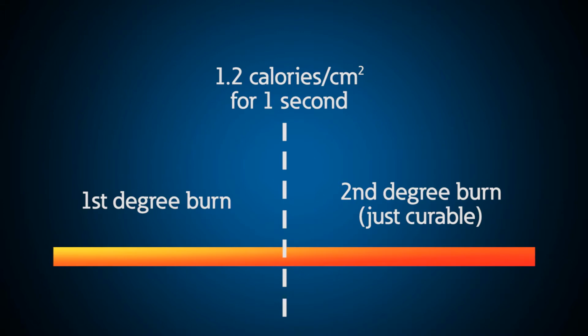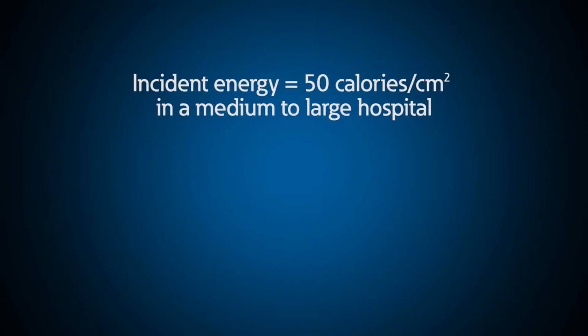It takes 1.2 calories per centimeter squared for 1 second impinged upon human skin to reach the threshold between a first-degree burn and a second-degree burn, which is often called just curable burn. Now, imagine an arc flash with an incident energy rating of 50 calories per centimeter squared, which is very possible in a medium to large hospital.